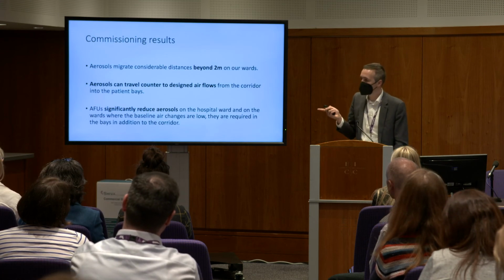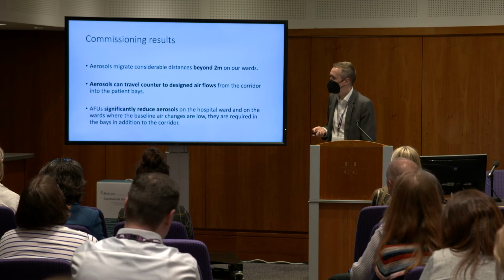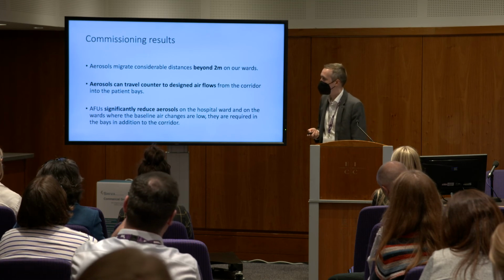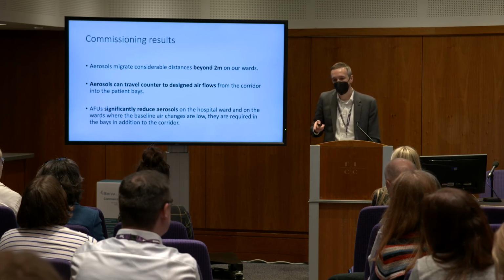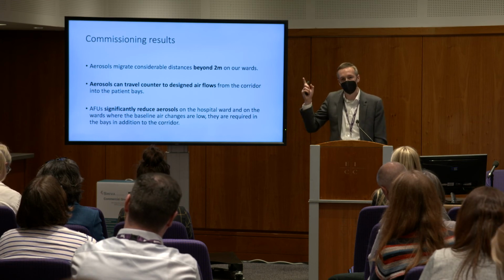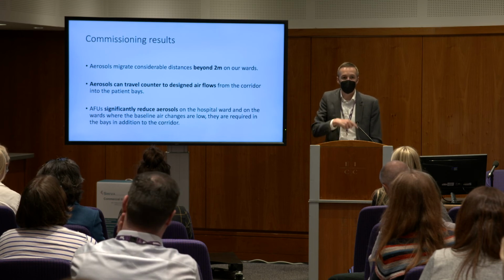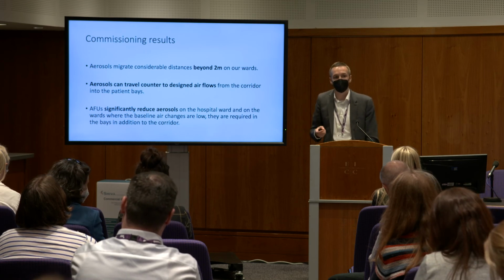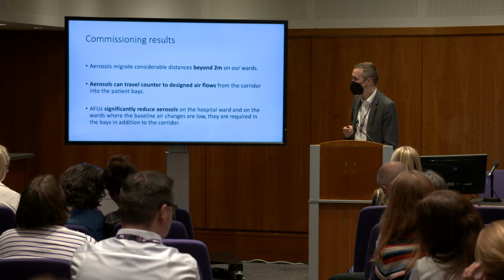So from our results, we basically concluded, well, obviously we knew this from people's work before, but they definitely go beyond 2 meters, and we've proven that on our wards. They also, and this is where you can never take anything for granted, can go against the airflows that you think are going. And that reiterated, if you think something's positive pressure, actually show that it's positive pressure. Or have a system that's alarmed such that if something happens and the ventilation fails, you know that it's failed. You don't have to wait for someone to get an infection, for it to spread, before you look into it.